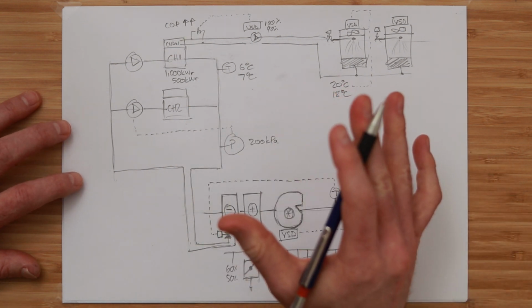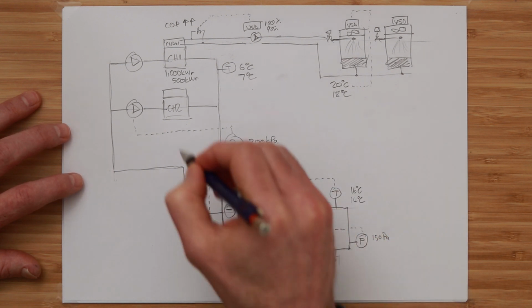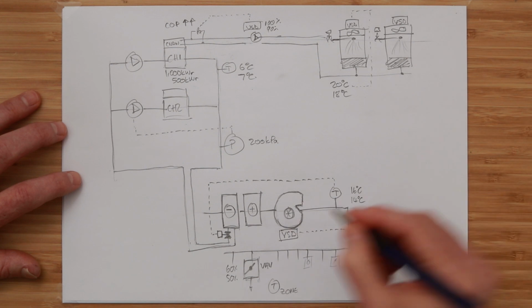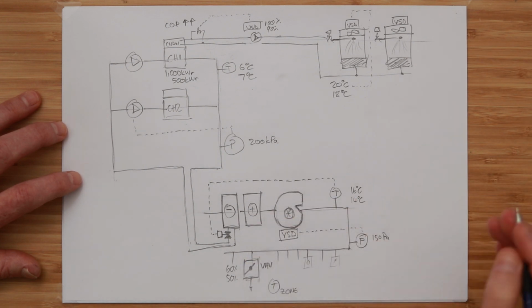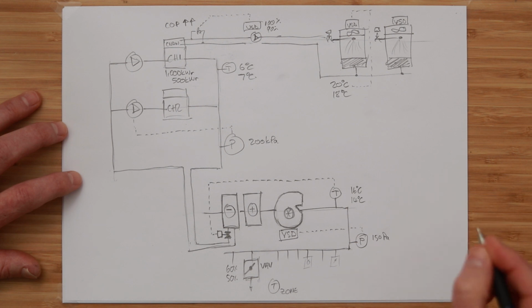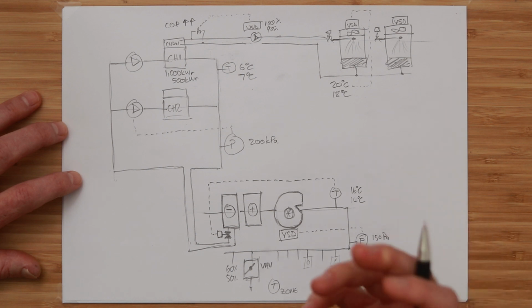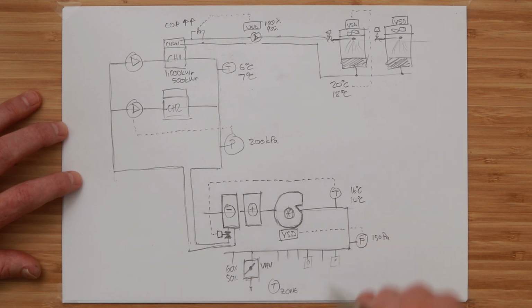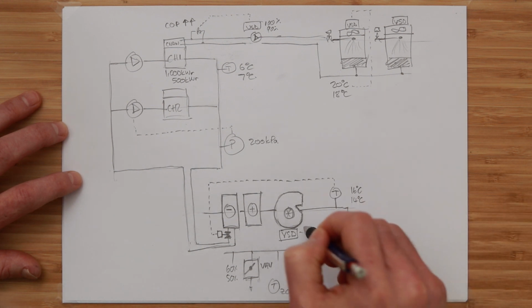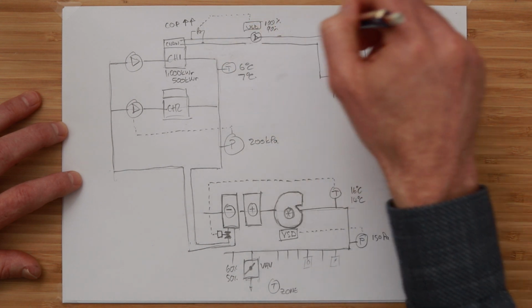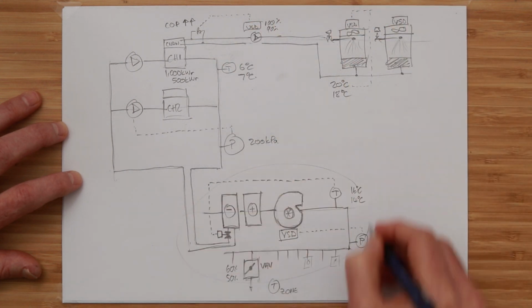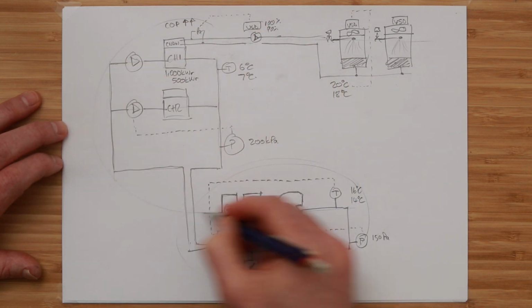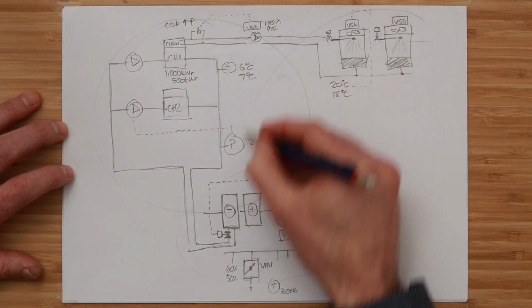The bottom line here is, and here's the point of the video, every single one of these multiple optimization strategies in isolation saves energy, tick in the box, let's do high fives. But almost always, when you optimize one system, it almost always negatively impacts some other system somewhere else. Now, us as human beings, and with our current BMS control strategies, which we've been implementing in Australia for 10 years, we are good at optimizing all these different control strategies. We can optimize the air handling unit. We can optimize the chilled water system. And we can optimize the condenser water system.